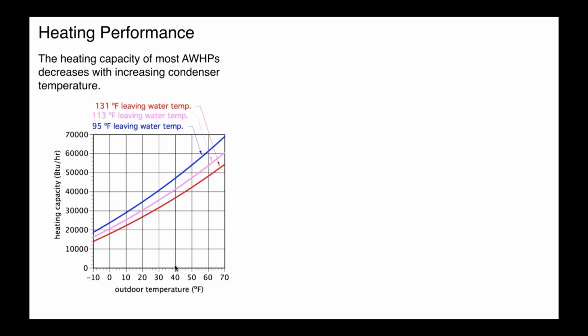So if it's 40 degrees Fahrenheit outside and we're trying to produce 131 degree leaving water, we have a certain capacity here, maybe 37,000 BTUs per hour. But if we were to only require 95 degree water, we're substantially higher. We're up maybe 47,000 BTUs per hour. Percentage-wise, that's a big increase. So what is this telling you?